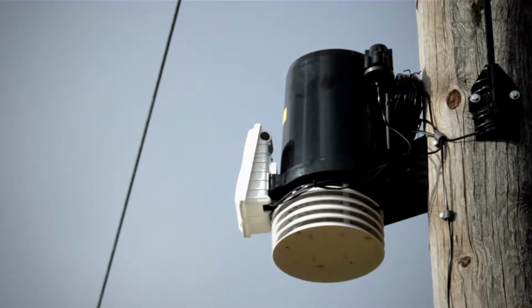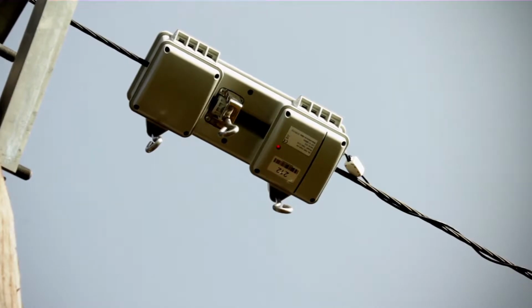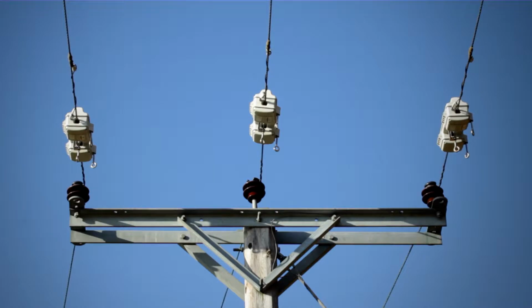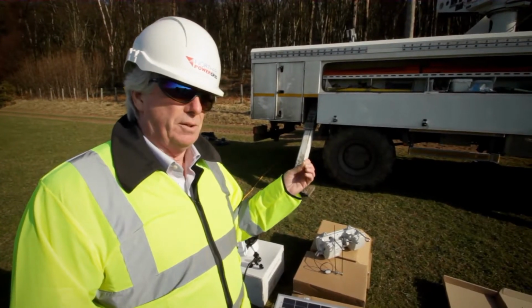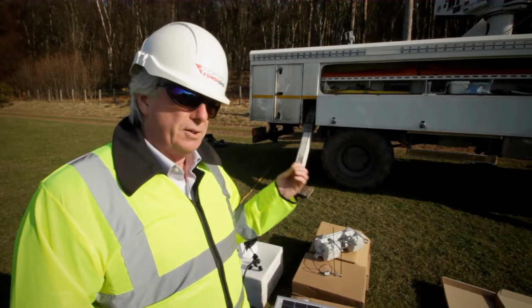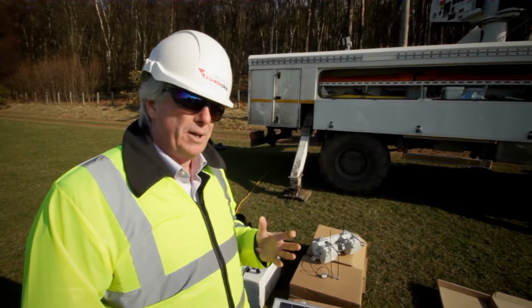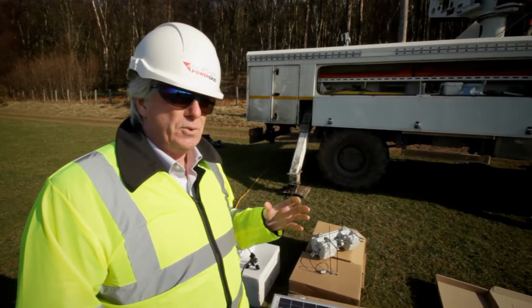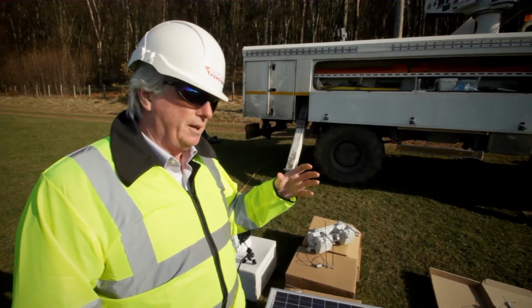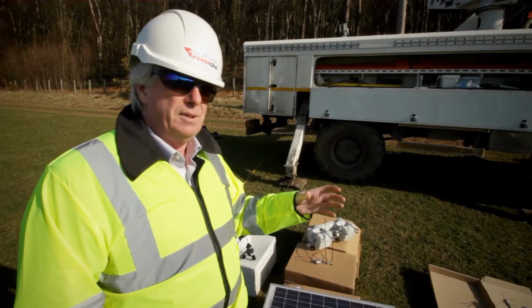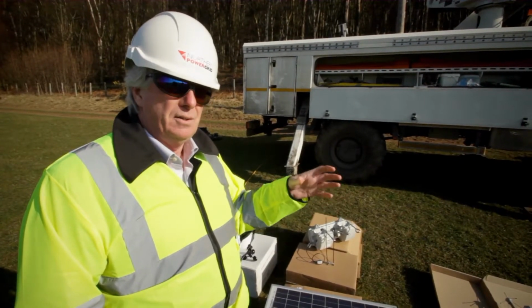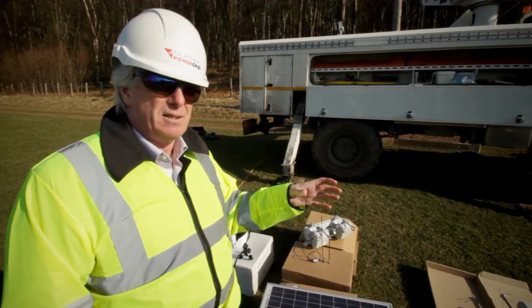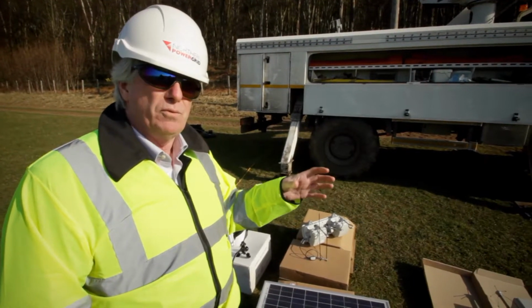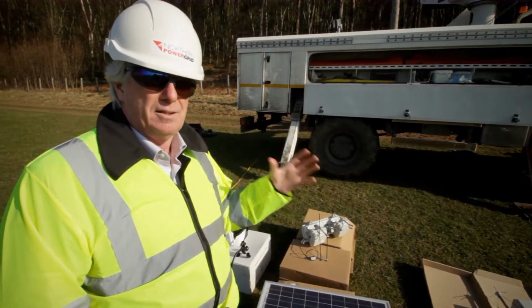Every 5 minutes there would be a report sent back to a server with data from the power line sensors installed on the conductor, with the surface temperature of the conductor, the current flowing in the conductor, and all the weather parameters. All of those parameters are then analysed by the other teams in the project to assess what's the best approach for dynamically rating this type of circuit.